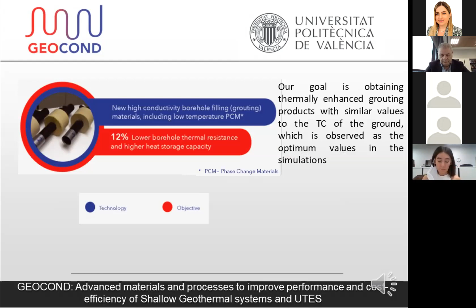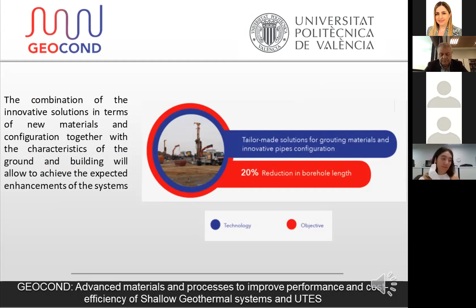The combination of the innovative solution, including the pipe and the grout, will lead to the production of this tailor-made grouting solution. It will be responsible for a significant reduction in the total length of the borehole field, up to 20%, associated with the shallow geothermal system. This represents an important saving during installation, and at the same time a compelling enhancement of the system's performance during its life cycle. So it's not only that you reduce the price during installation, but you also get better energetic performance throughout the life of the installation. Considering that the standard life of these systems is 25 to 50 years, this means a lot.